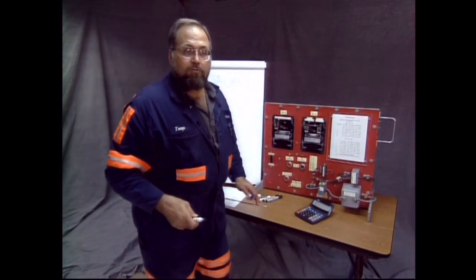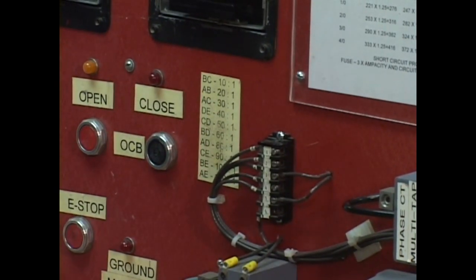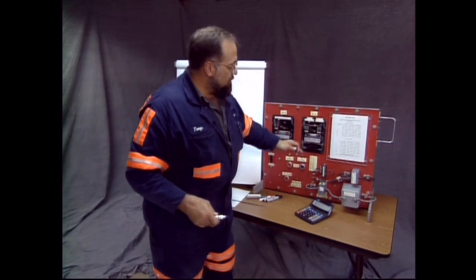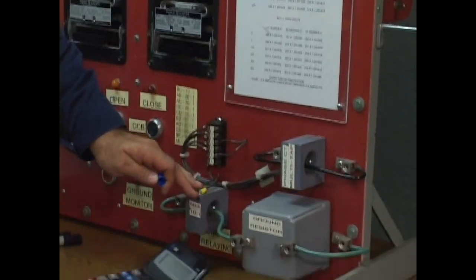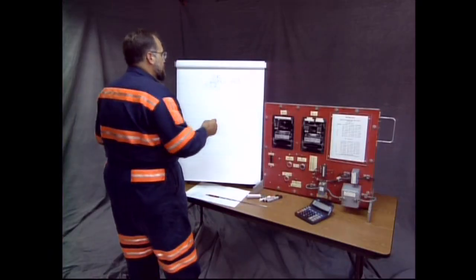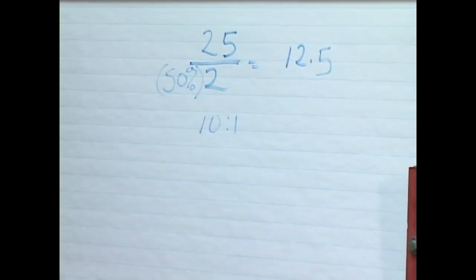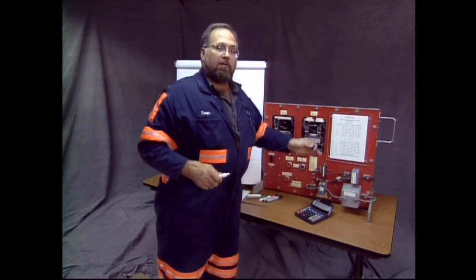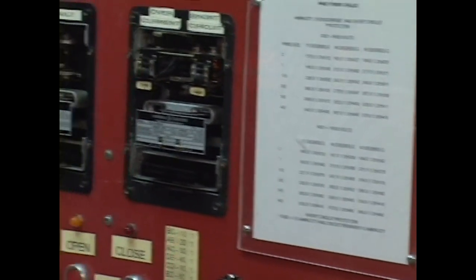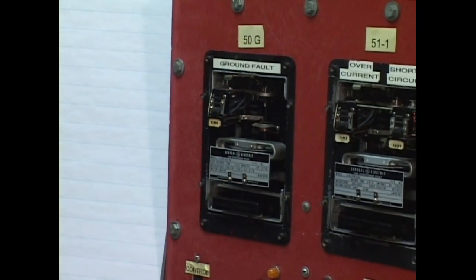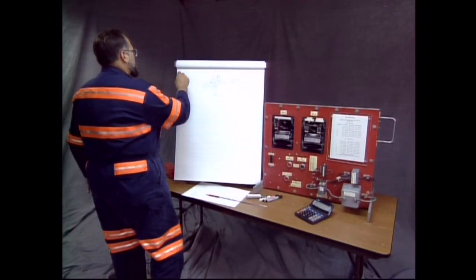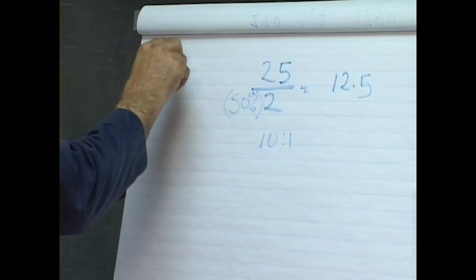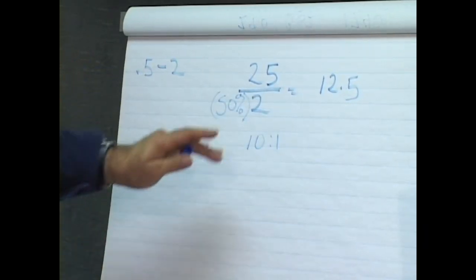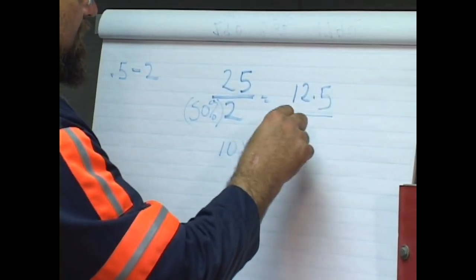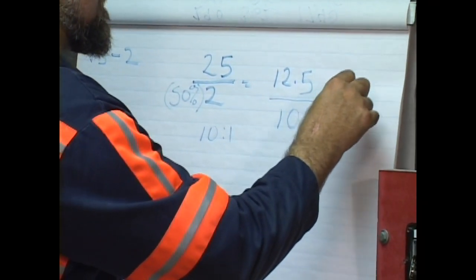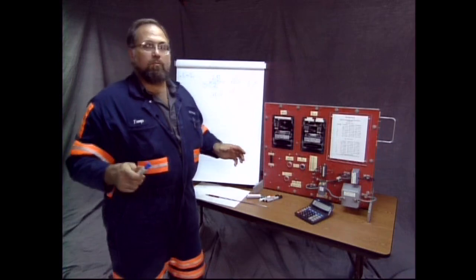Here we had all these different ratios to choose from, all these different ratios to accommodate the phases and the different cables to set each phase. The ground has one ratio. There's no selection process there. You have a 10-to-1. Now, if you remember, we divided the ampacity that we wanted by the ratio to get a tap setting. Well, we're going to be setting a tap here too, just like this one. Now the range is different. This one's 0.5 to 2. We're going to divide this 12.5 by a ratio of 10. So 12.5 divided by 10 equals 1.25.